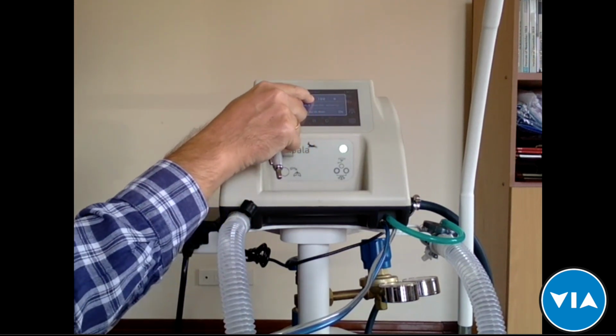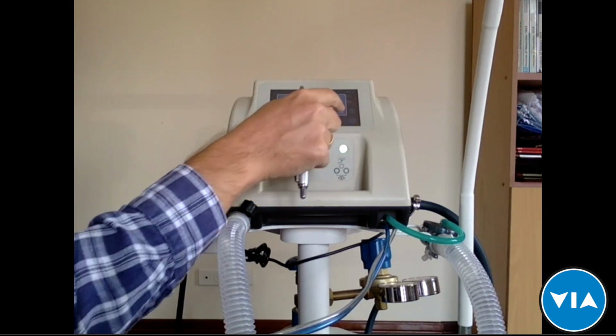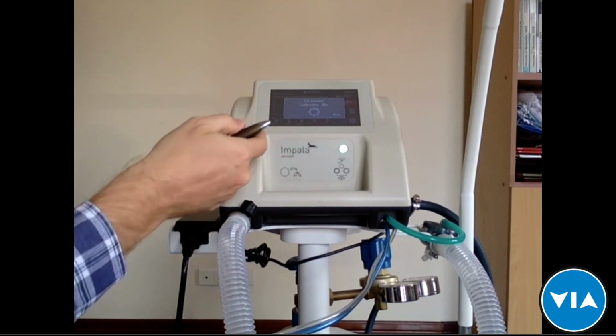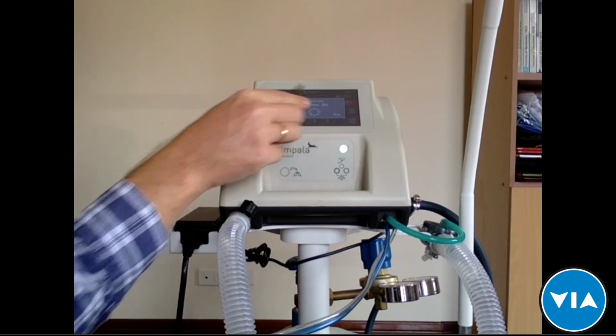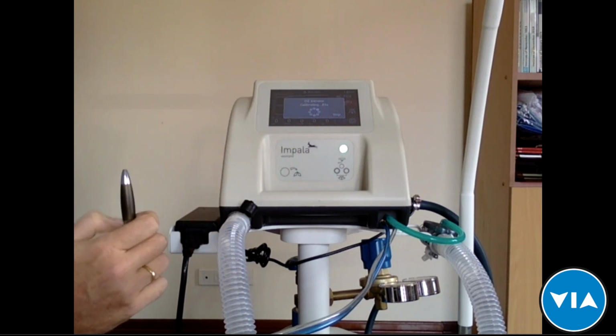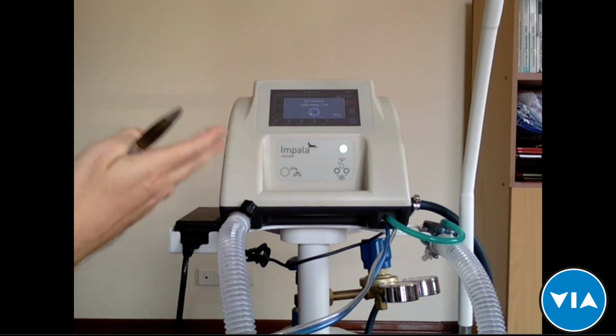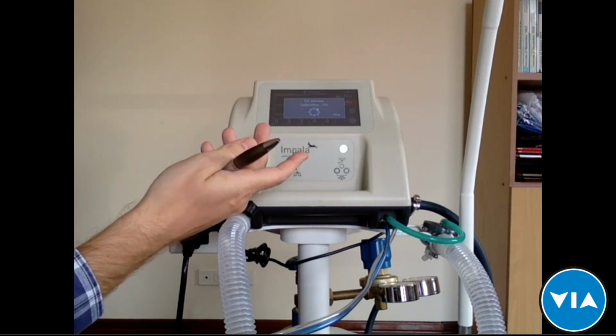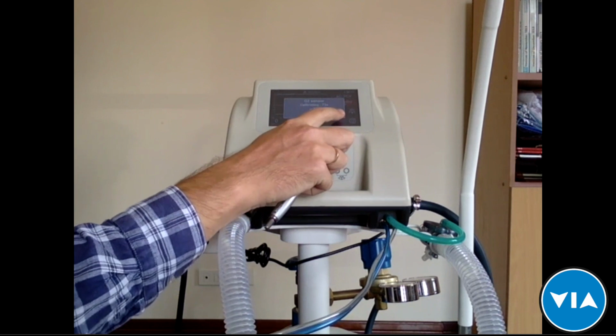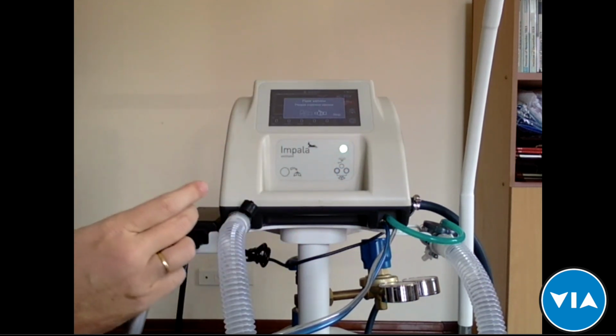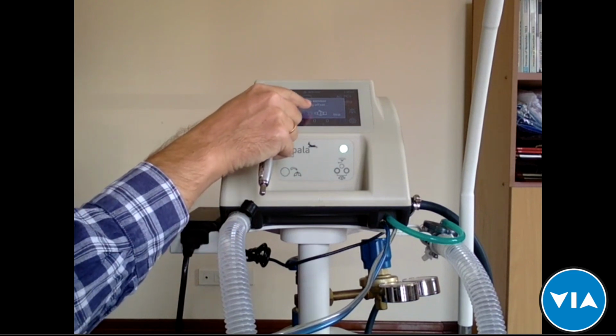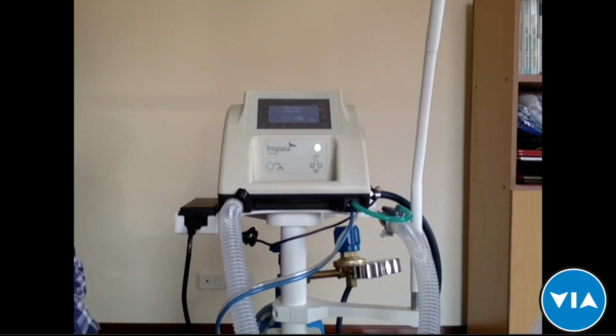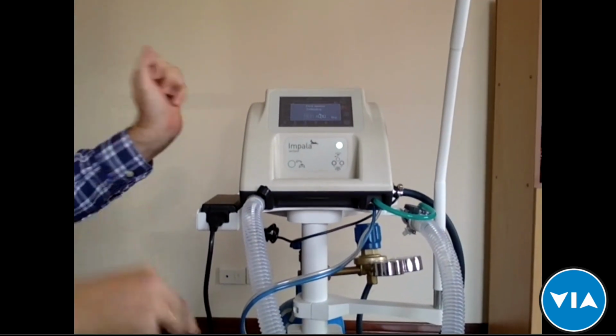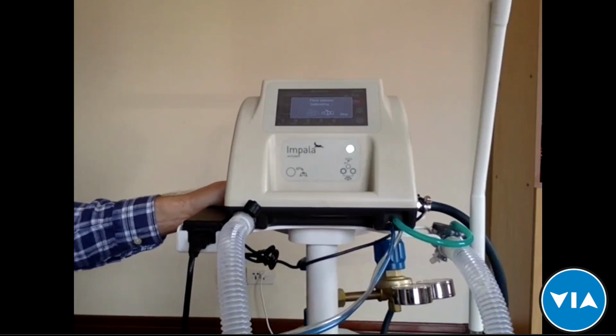So let's say that the female is 160 centimeters tall. We accept that. And we go into calibration, oxygen sensor calibration mode. It takes 90 seconds. We can hear it. And once the calibration is done, or I skip it because obviously we don't need to wait 90 seconds, it can be skipped. We go into the flow sensor calibration mode, which is also important. The flow sensor here, just as a reminder, is being calibrated. And now we can see on the screen that the calibration is taking place.